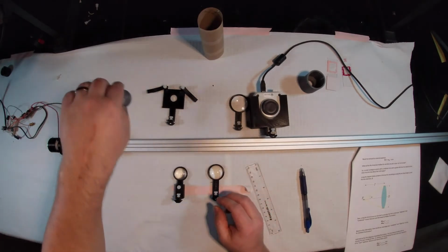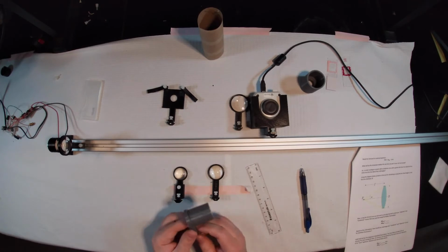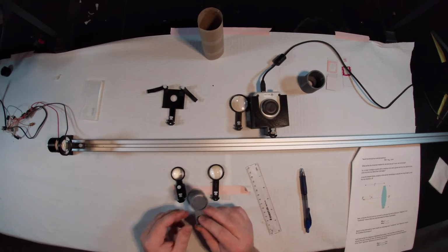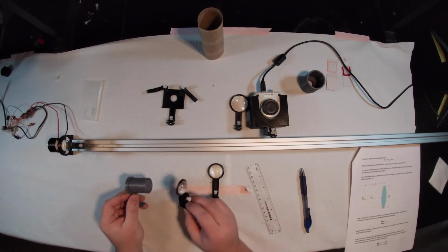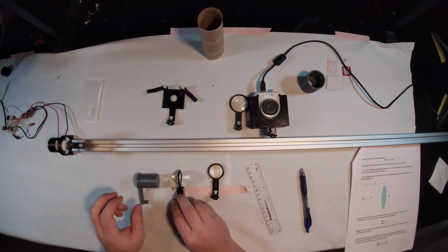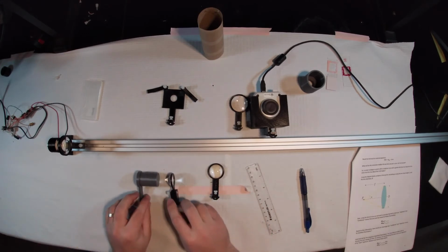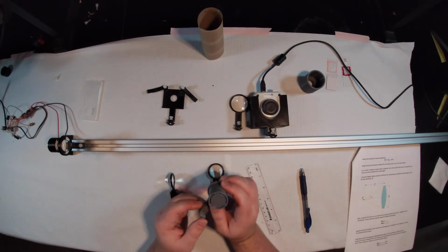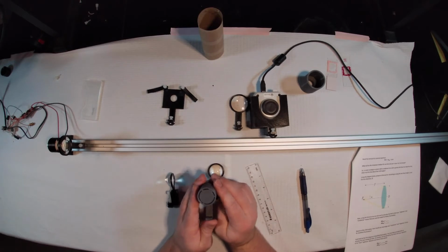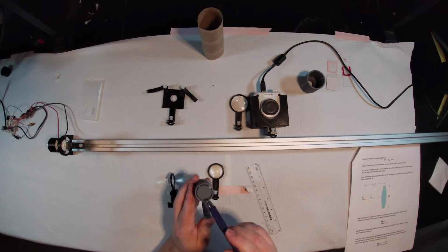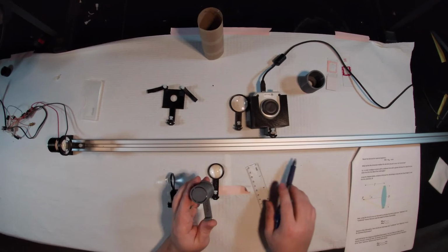So finally, for darkfield, you do need an annulus. This is going to be placed somewhere behind the condenser lens that we are actually using, the objective lens that's being used as our condenser in the system. We will find a place somewhere behind it that we will use to restrict out the lower angle light and let through just an annular sliver of light.